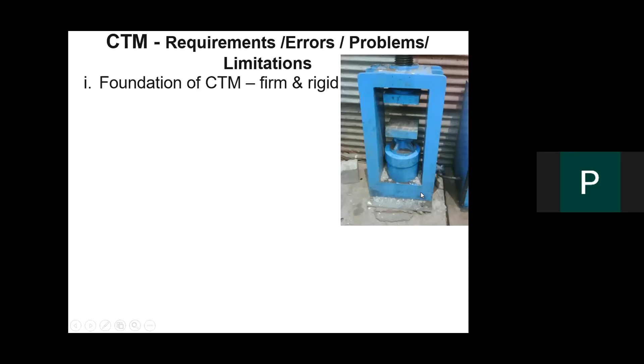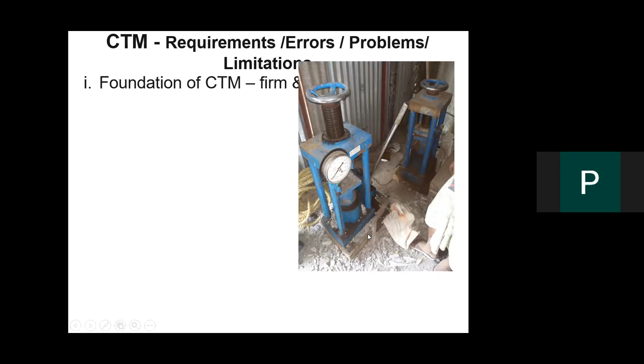I have seen many machines which are on wooden planks, put on the ground, and what happens whenever there is loading, instead of breaking the cube, I had seen the plank or wooden system bend, because the machine is not giving its load to the cube, it is giving a load to the bottom foundation. So if the foundation is not properly made and rigid, there will be variation in your readings or results.